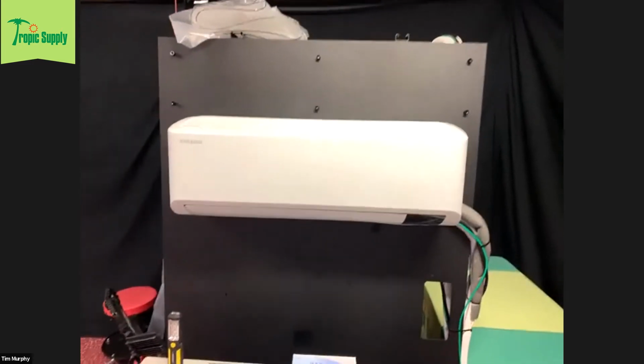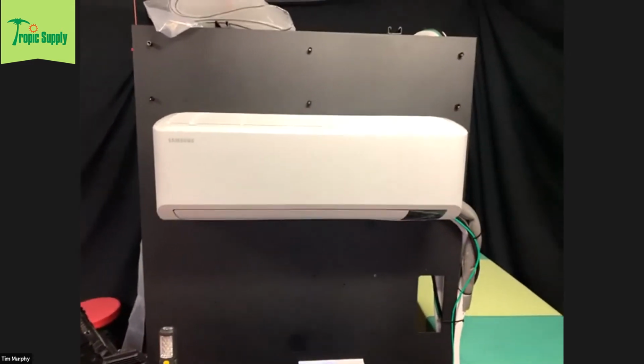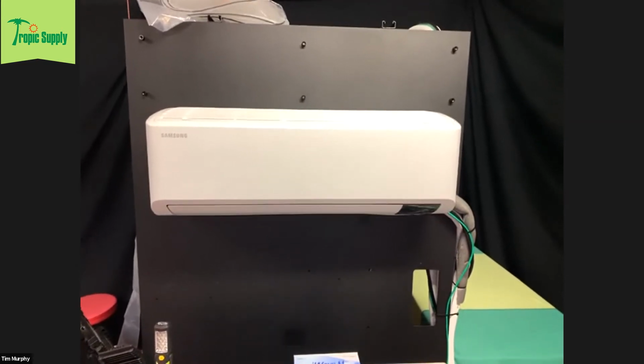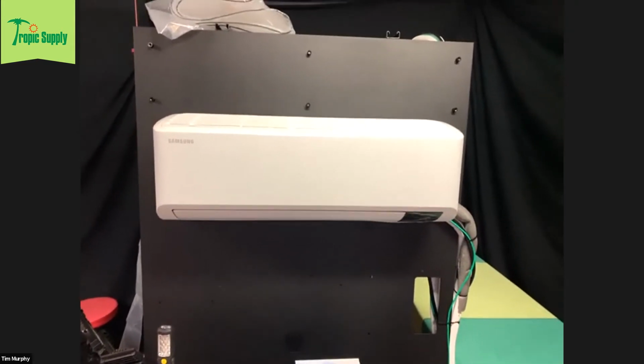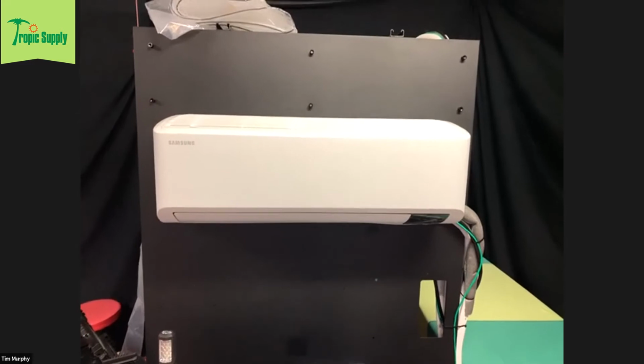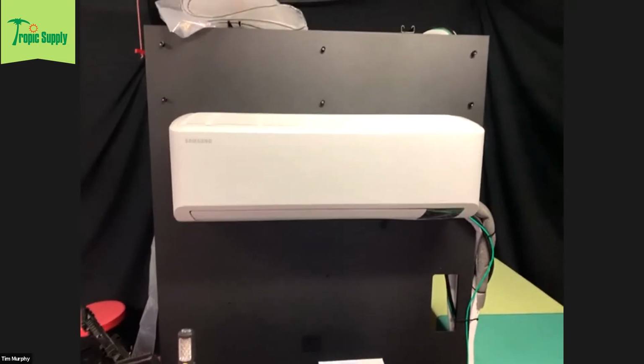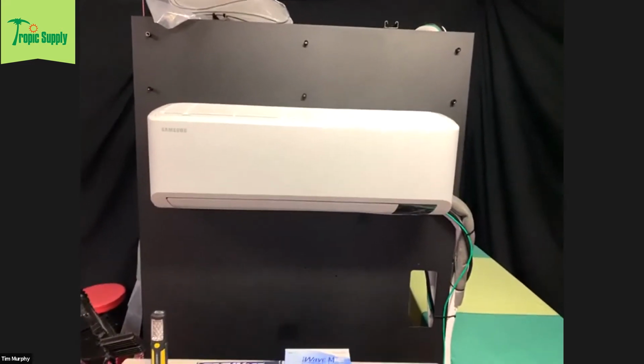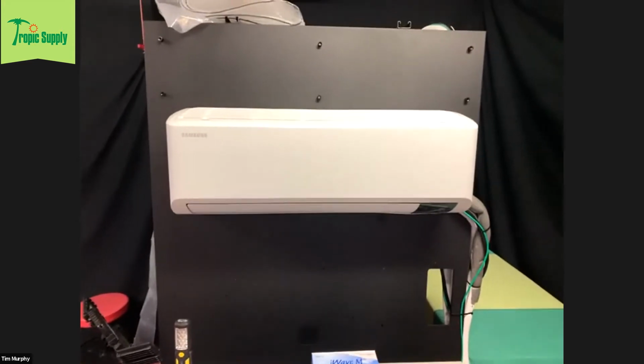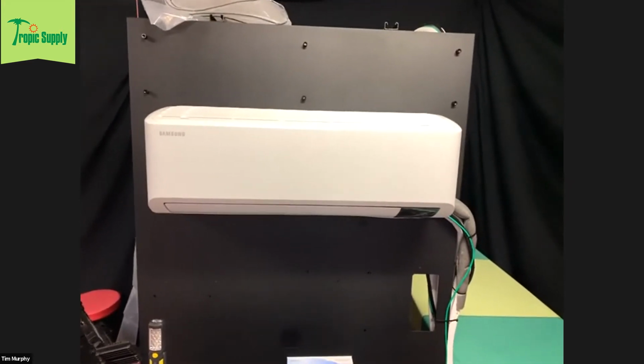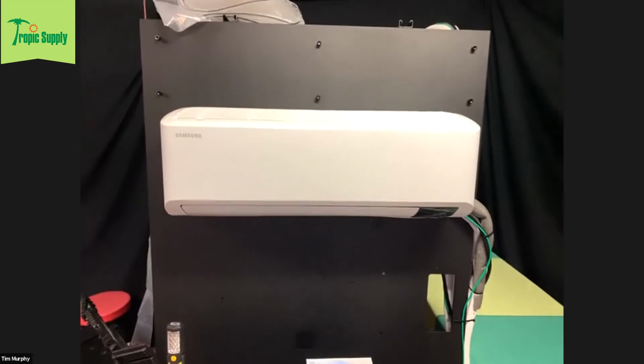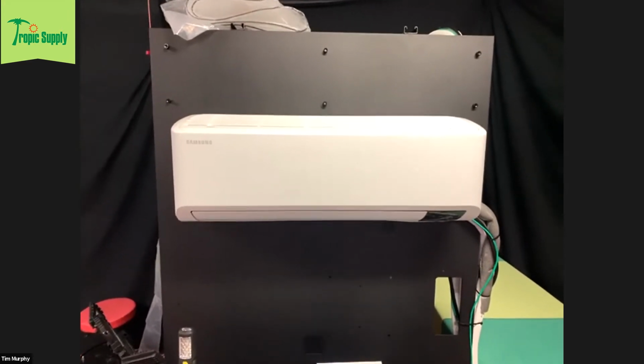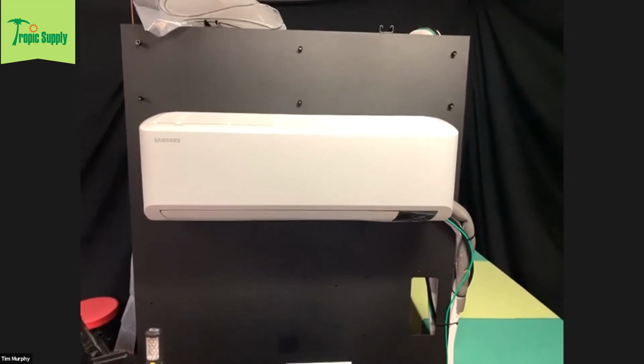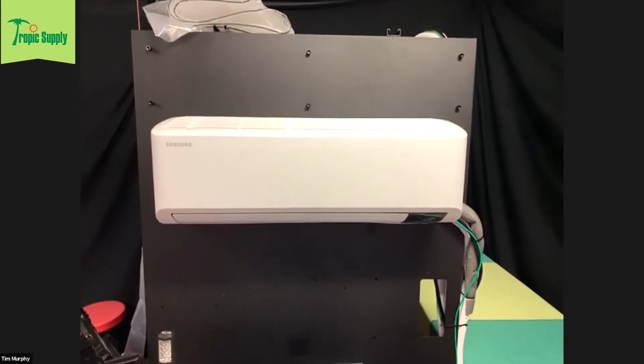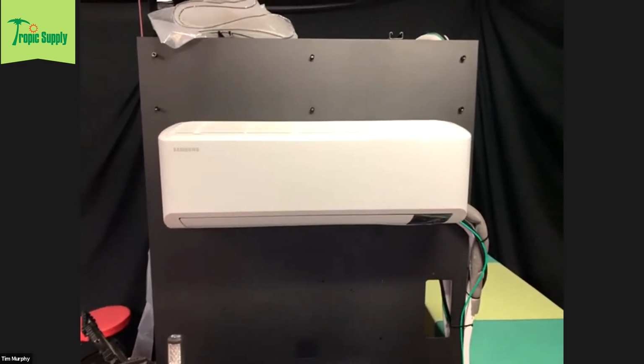Now, what I've seen in the past with different systems, some of the older ones, you may have to go into a pump down mode depending on the brand. I'd suggest looking into that per manufacturer. What I've done in the past, when I had my technicians and installers in the field, if they went to a system we didn't install and wasn't a brand we worked on often, the safest bet if you're unsure would be to just reclaim the Freon.